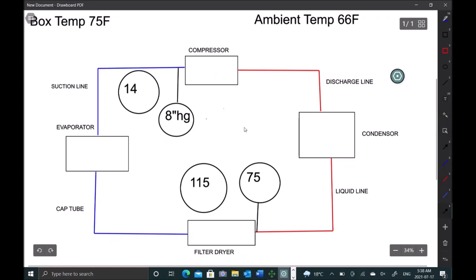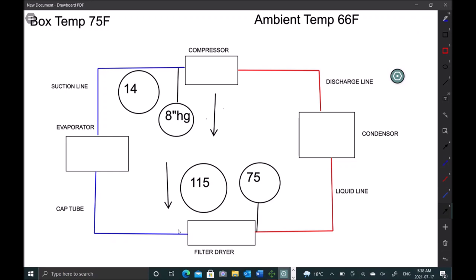And based off of that, it's telling us our suction pressure is low, our head pressure is low. Okay, so there's only two reasons why we'll have that on this cap tube system. And it's either low charge or a restriction in the system. So let's go rule out our restriction in the system first and see if that's the issue. And if it's not, let's go hunt for a leak.